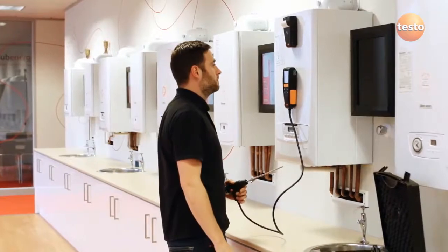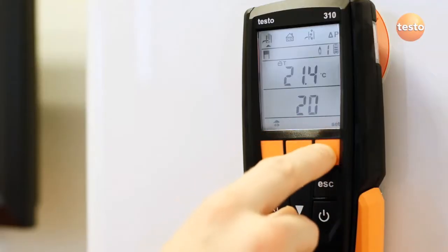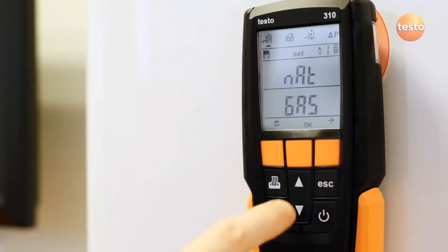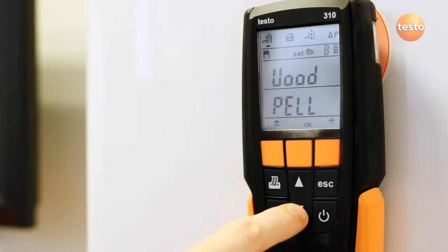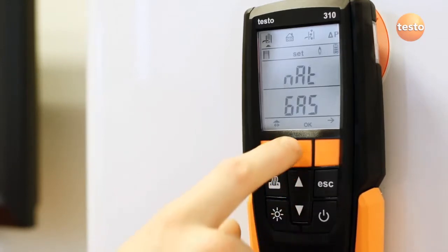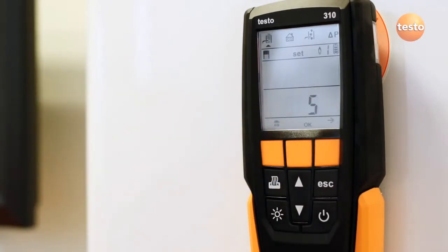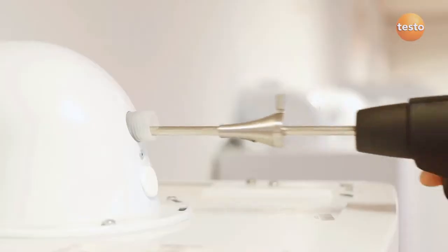While the sensors are zeroing, which takes 30 seconds, you can choose the fuel type. Press Set, which is the right-hand orange button, and then scroll through the list of fuels. Select the required fuel and let the analyzer finish zeroing. Now you can put the probe in the flue.